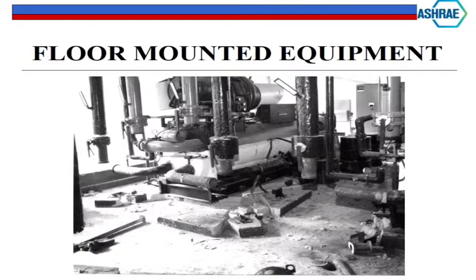So this hospital, this happened to be the 3rd floor of a hospital. This hospital had seismograph equipment on that floor. It saw a 1.1 vertical G input. So the idea is we think when the input went up, it actually threw the equipment up in the air. I mean, you know, maybe this much, whatever it is. But it lifted it off the ground, came back down, and it shattered like a pane of glass. And that's what it ended up looking like, right? Because there was no reinforcing, all right, no attachment, no doweling into the structural slab. So that really isn't a load path that is complete to move all the forces down to the structural slab of the building.